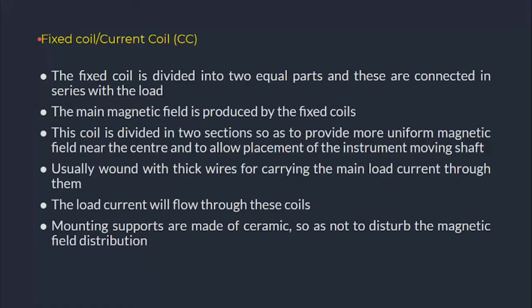The fixed coil, or current coil, is divided into two equal parts connected in series with the load. The main magnetic field is produced by these coils, which are divided into two sections to provide a more uniform magnetic field and to allow placement of the instrument moving shaft. These fixed coils are wound with thick wires for carrying the main load current, and their supports are made of ceramic so as not to disturb the magnetic field distribution. That is why it is also called the current coil.